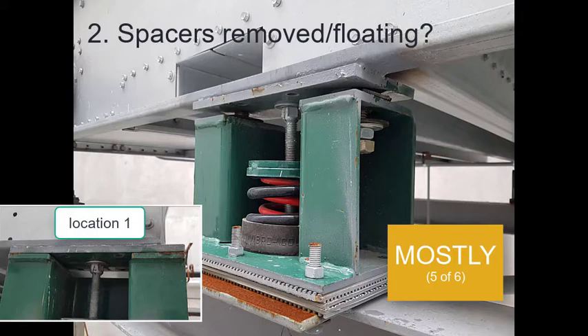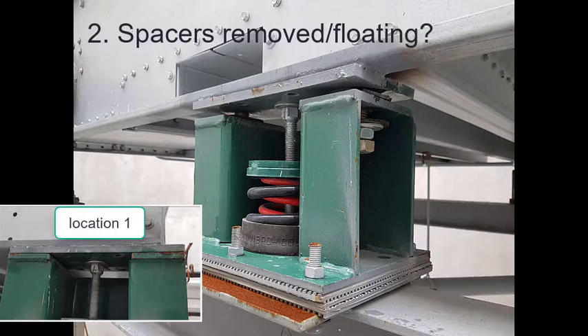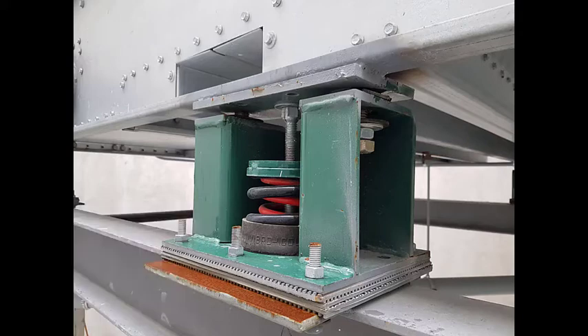Items in this category typically only need to be addressed if they create additional problems, or if there is evidence of structure-borne noise, or if there was a need to certify the installation. If that were the case, we would need to mark this as something that would need to be corrected. Correcting this requires the contractor to lower the tower back onto the spacers where they can be reinserted and then proceeding to put weight on the springs in the manner and method described on the installation instructions page.